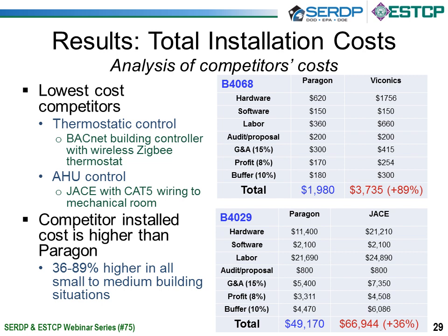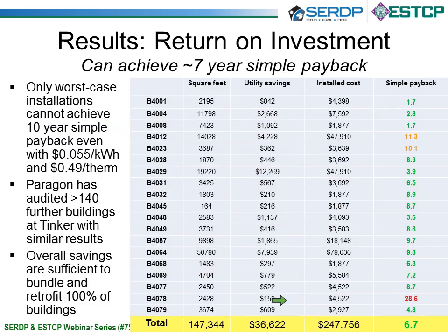So although the costs here, once we got into it, were a little higher than we initially anticipated just because of the extra overhead and costs working on DoD facilities, we were able to get a little bit more energy savings than we initially anticipated as well. So the end target for most performance contracts, as a rule of thumb, is a 10-year simple payback. That's usually enough to automatically allow funding using performance contracts. So our target was anything less than 10 years, and we were able to achieve a little bit better than 7-year simple payback across this entire sample of demonstration buildings.